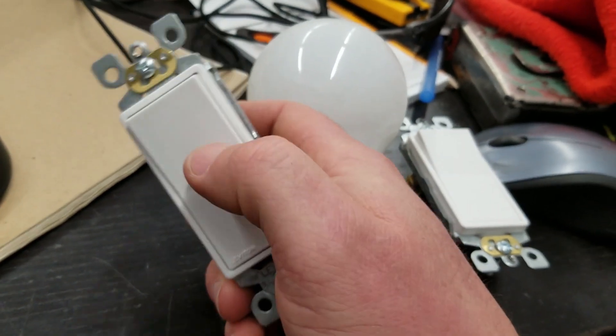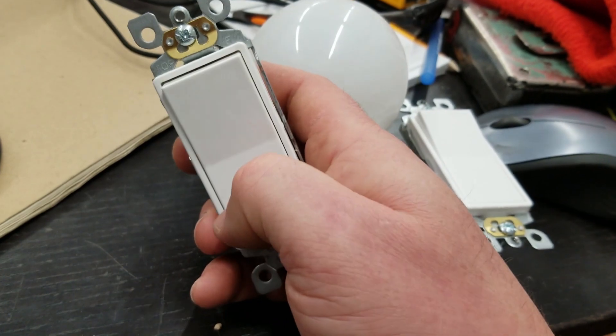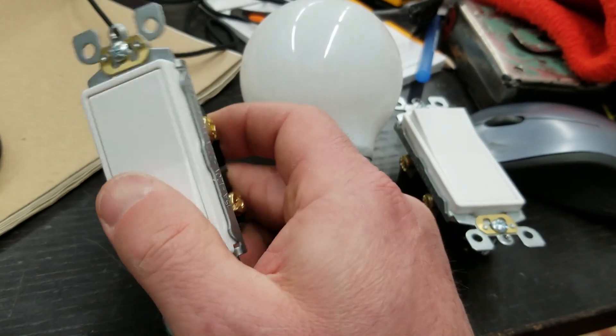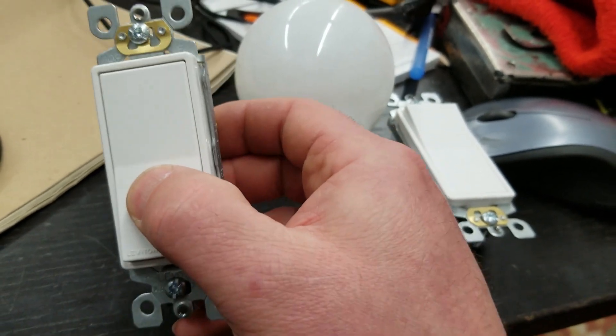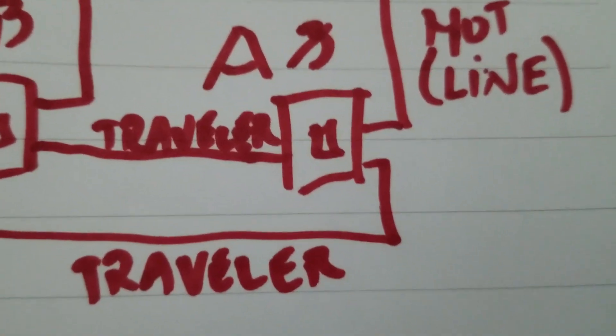Switch A is an entirely arbitrary label - it could be alpha for all we care. What we're worried about is the box, what's got the hot in it. Identified the hot line in switch A. That means the other two are travelers.